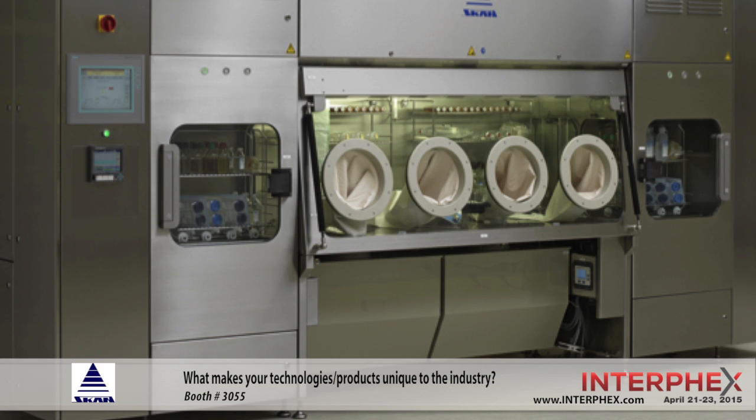We've really taken this to the next level and we're very excited about the technology that we bring to bear. We also utilize our hydrogen peroxide knowledge to understand how the hydrogen peroxide interacts with the product. For example, low-level residuals of hydrogen peroxide may have a slight impact on your product. We have measurement technology in our labs where we can measure down to the two to five parts per billion range and actually detect hydrogen peroxide in your products and in your container packages. It's very important to understand what's going on with your decontamination process — it's much more than just getting kill of biological indicators.